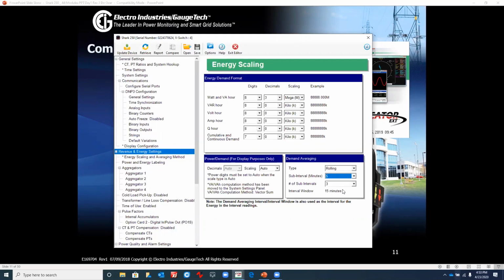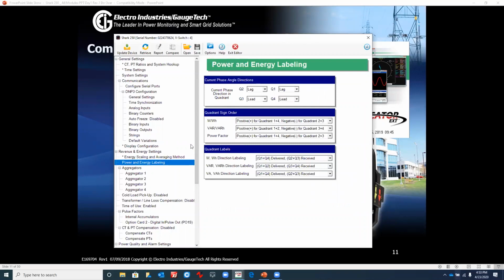In a block, the block average that we talked about before, the block is just take an average number of whatever those are. So it typically is lower than what you will find for the 15-minute period than a rolling. So utilities like to use the rolling because it produces the highest demand over 3 5-minute intervals for a 15-minute sample period. Energy scaling we talked about, so let's go to power and energy labeling.